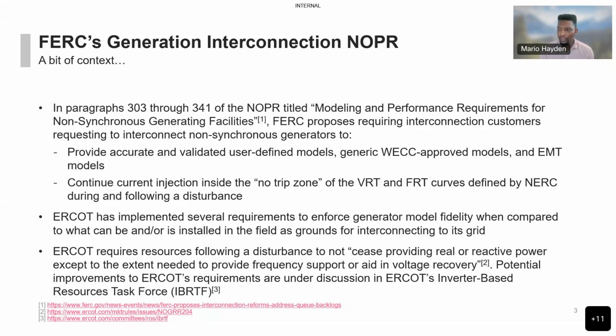For the ERCOT piece of this, ERCOT has implemented several requirements to enforce generator model fidelity since at least 2017, if not earlier, which make sure the models submitted are accurate and parameterized in a way that doesn't create issues in studies, but also that the parameters can be matched to things that can actually be installed in the field. Secondly, regarding the ride-through piece, ERCOT does have current requirements for ride-through, which have been discussed at length in the IBRTF, the Inverter-Based Resource Task Force, though that won't be the main topic of this conversation.